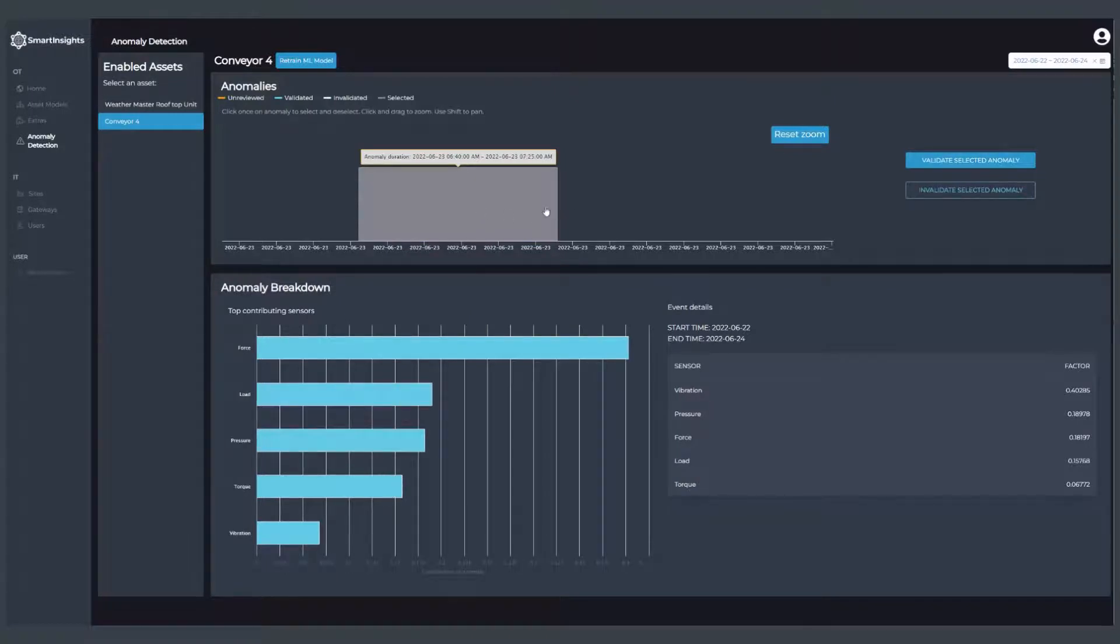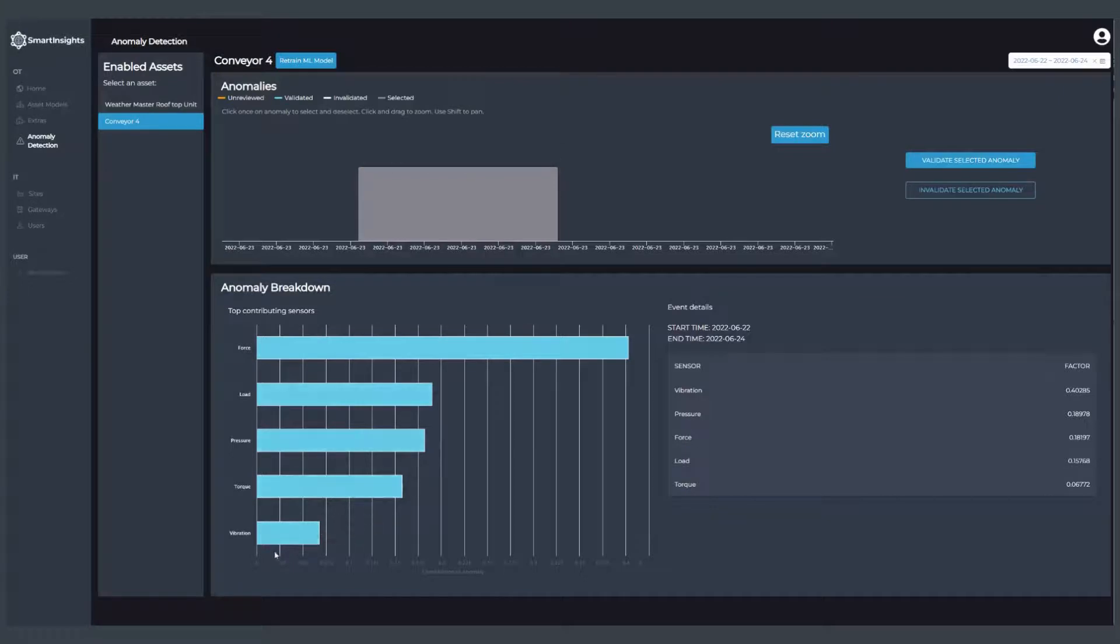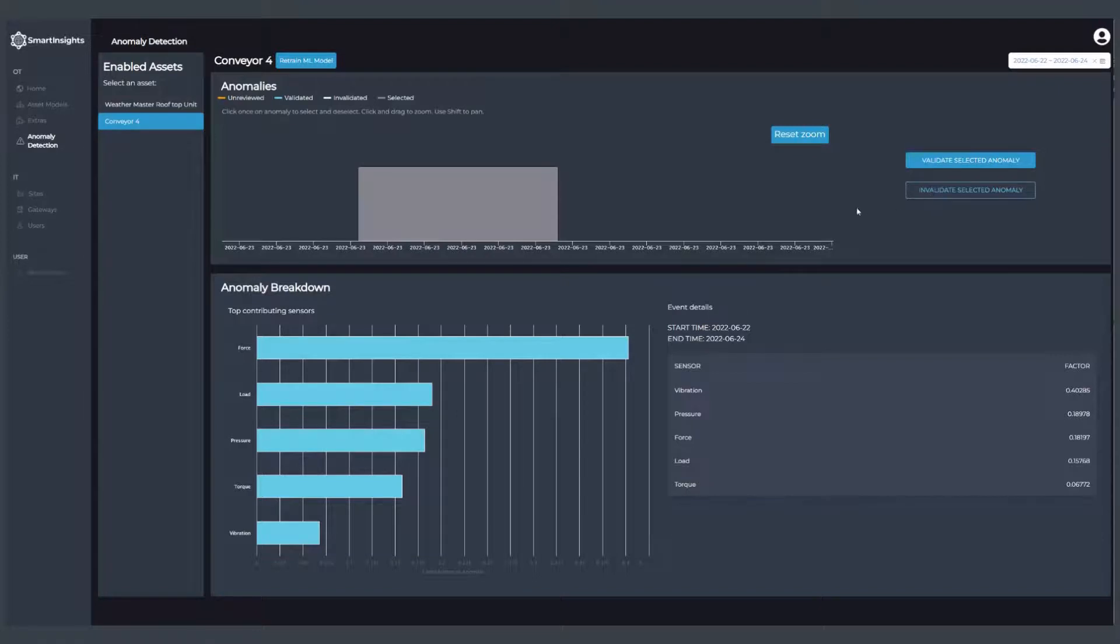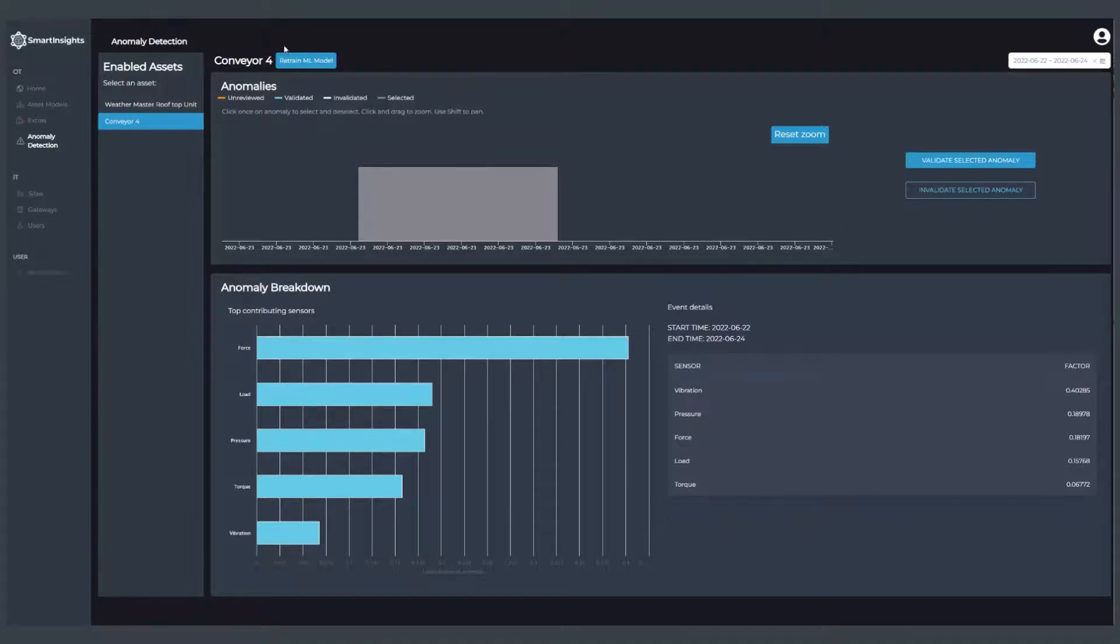If we see an anomaly, we can click on it for more information. We can see all of the sources of data that are contributing to the machine learning model identifying an anomaly in the equipment. Then as a process engineer, I can either validate or invalidate that anomaly to train the model over time, so I can use this for predictive maintenance and other types of use cases. I can retrain the model directly within Smart Insights.